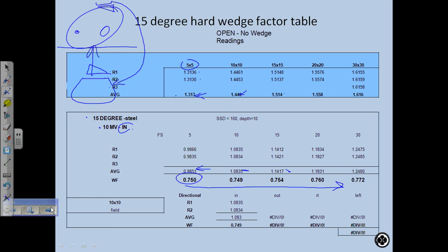Okay. Thanks. So, since you actually got a lower factor on the 10x10 and the 5x5, would that make you go back and redo it? Or well, look at the difference. It's within experimental measurements. So you wouldn't worry about that. No. That's really small. That's a 0.1% or 0.2% difference. I'm not worried about that.